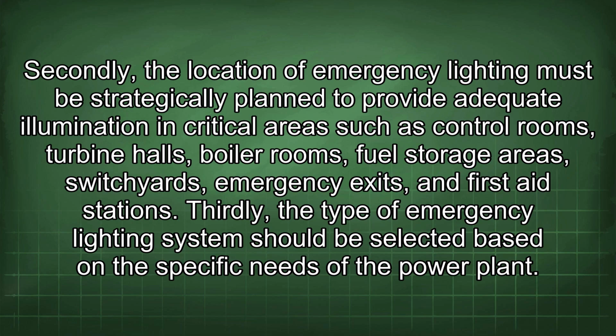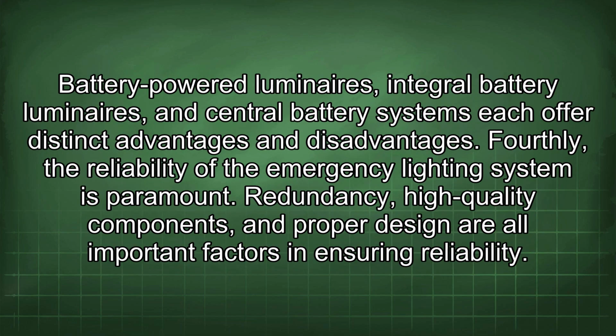Thirdly, the type of emergency lighting system should be selected based on the specific needs of the power plant. Battery-powered luminaires, integral battery luminaires, and central battery systems each offer distinct advantages and disadvantages. Fourthly, the reliability of the emergency lighting system is paramount. Redundancy, high-quality components, and proper design are all important factors in ensuring reliability.